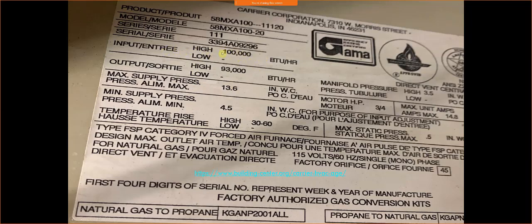The other thing that I'm starting to get off of this data plate, I've got an input of 100,000 BTUs. I have an output of 93,000. What this means is if I do the math, I have a 93% furnace. What that means is if I have a 90% or greater furnace, I'm going to have to use PVC exhaust and intake tubing. There's moisture that's created through the combustion process of the unit, and that moisture can get inside the PVC pipes, and if it was a metal pipe, it would rust. So if I had an input of 100,000 and an output of 80,000, I would have an 80% furnace, and I generally have a 4-inch metal flue pipe sticking out of that, and that's just to carry the exhaust outside.